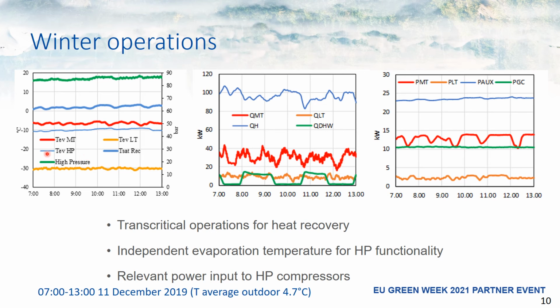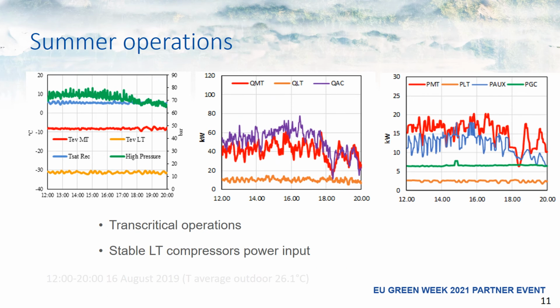And we can also see that the evaporation temperature of the outdoor evaporator can go as low as minus 10. Here you can see this blue line, and it's lower than the saturation temperature of the receiver, which is much higher here. And this is because of the outdoor temperature, which is in this case quite low. We can also have an idea of the loads here, where we can see that the heating demand is as high as 100 kilowatt, and this of course corresponds to a high energy power input to the auxiliary compressors. During the summertime, we can see again operating parameters, loads, and electrical power input to the compressors.